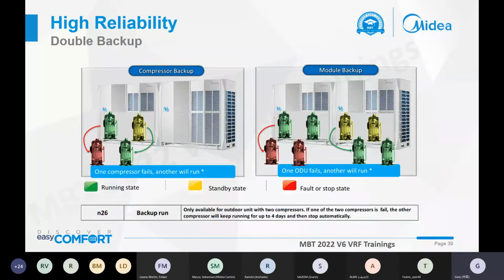And the double backup. This function is used when one outdoor unit has multiple compressors. If in one unit one compressor breaks down, we can make this unit run with only the other compressor. So this is very useful. When one compressor is broken and the remaining one keeps running, it makes sure that our system keeps running and provides basic cooling and heating.